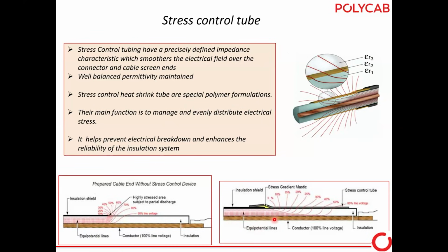Now see the second photo. We have used the stress control tube here. The stress control tube is the tube which deflects these stresses. These stresses were concentrating at this point. Now, stresses are not concentrating at that one point; they are getting deflected. That is the function of the stress control tube. There is also stress grading mastic. Because the semiconducting layer has a step here, we use stress grading mastic at this point. So this is the function of the stress control tube, and it is very, very important.